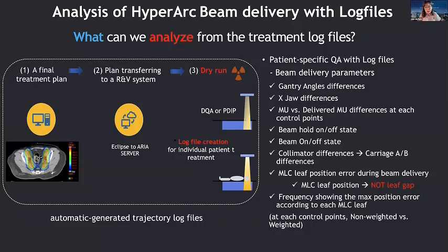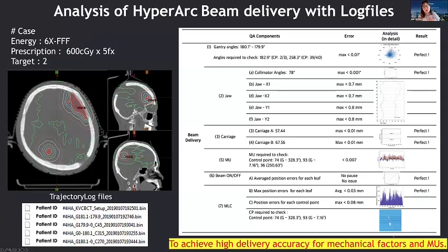So I analyzed HyperArc's delivered patient log files. When we analyzed the representative case, we found, very surprisingly, that the machine was working very accurately at every single point. For example, if you look at the gantry and the carriage angle here, the maximum error is less than 0.01. That's why we could see that result through the QA devices. It was really good, and every time it passed. And the delivered dose is in very good agreement with the planned dose.